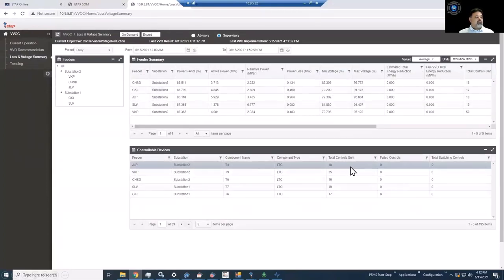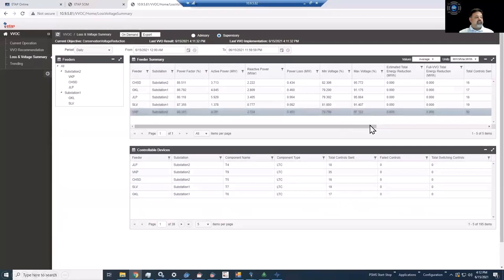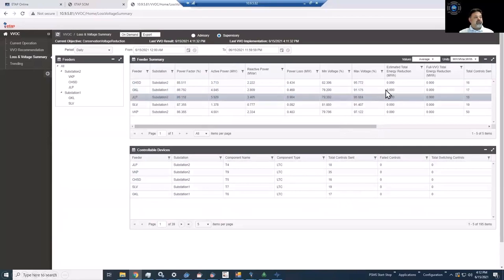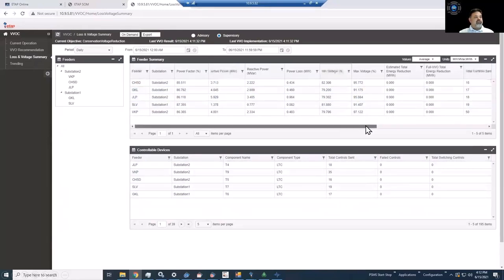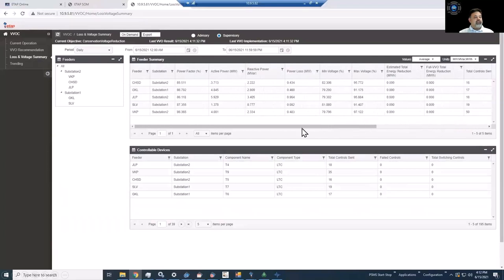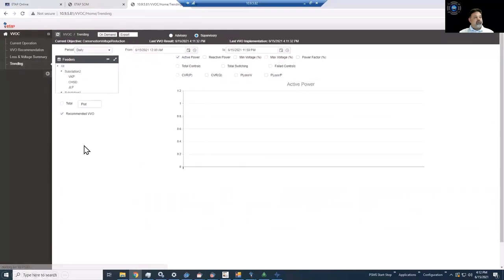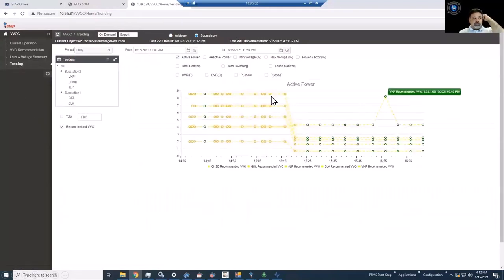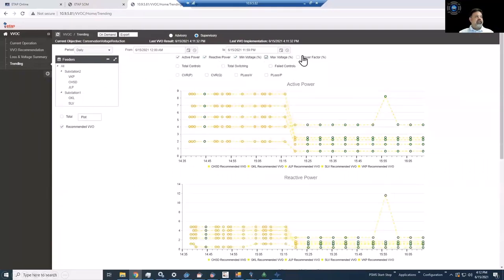Here, for example, we are looking at the transformer load controls. You can see the values that have been validated and optimized by the VVO. We can also look at this in the form of charts, where we can see voltage levels, reactive power flows, maximum voltage levels, maximum power factor, VAR controls, and so on.